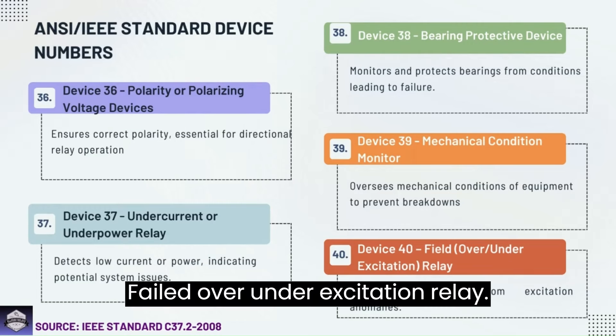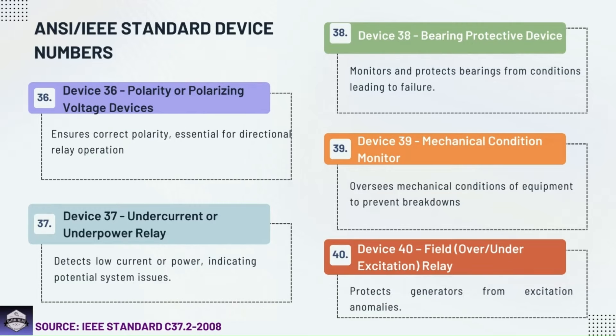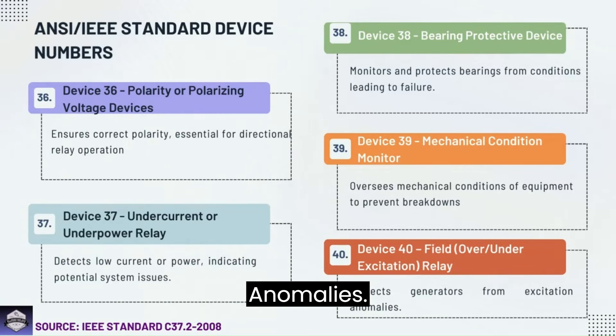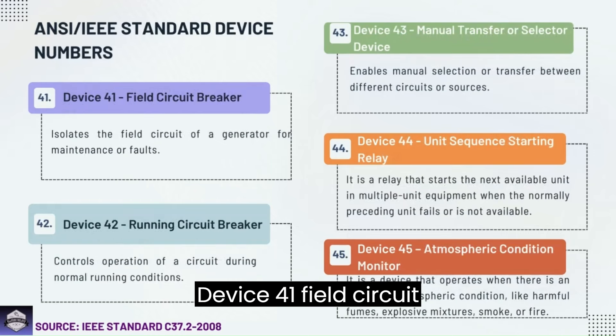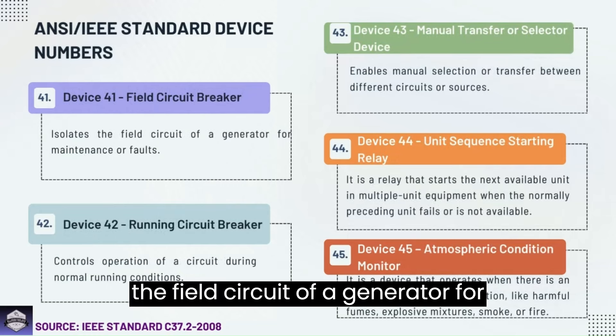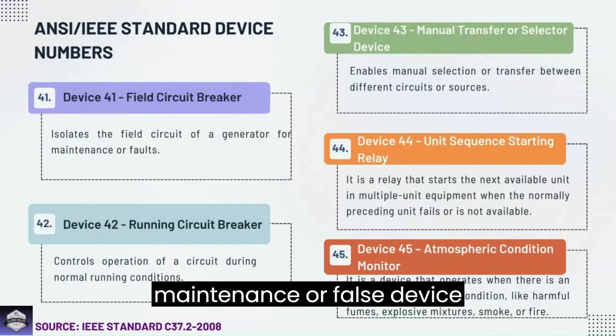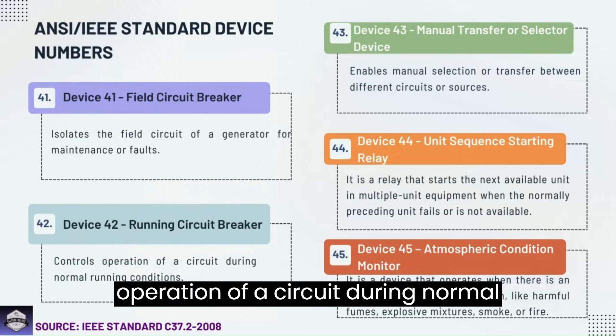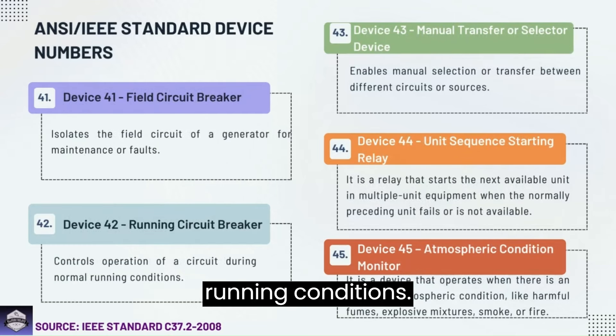Device 40: Field over or under excitation relay — protects generators from excitation anomalies. Device 41: Field circuit breaker — isolates the field circuit of a generator for maintenance or faults. Device 42: Running circuit breaker — controls operation of a circuit during normal running conditions.